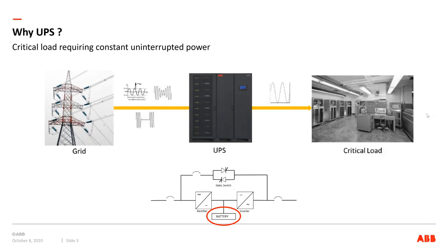The last power module in a UPS is a static switch. If something happens downstream from the UPS that the inverter cannot handle, the UPS control will fire the static switch and transfer the load directly to utility power. That can be in case of an overload or a short circuit downstream.